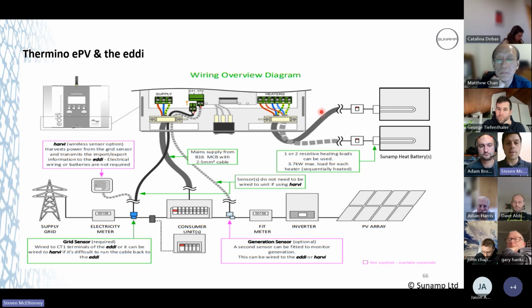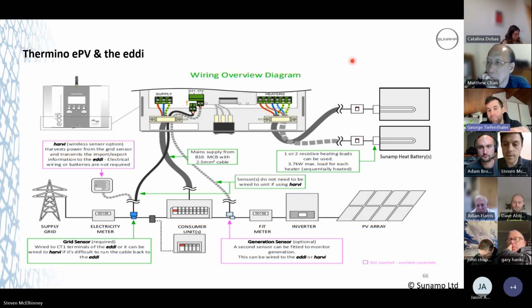All right, so does that make sense? Flow rate wise, you do get that, calculating just off your primary battery. If you've got a 150 primary battery, you can do 15 litres a minute. Obviously, if you have a secondary battery that's a 150, you're still only calculating to deliver 15 litres a minute because you can't guarantee that secondary battery.